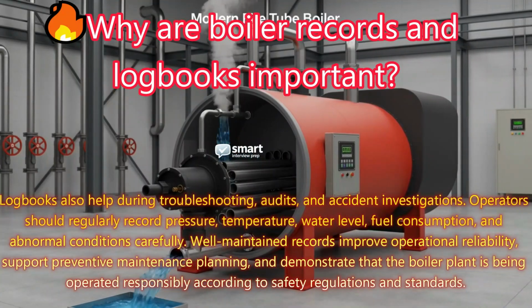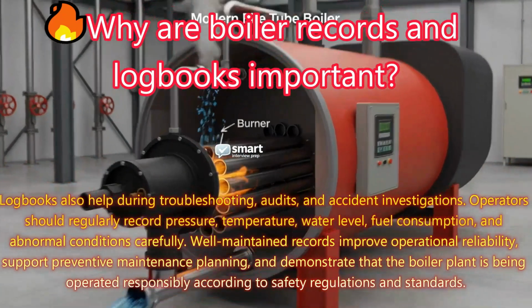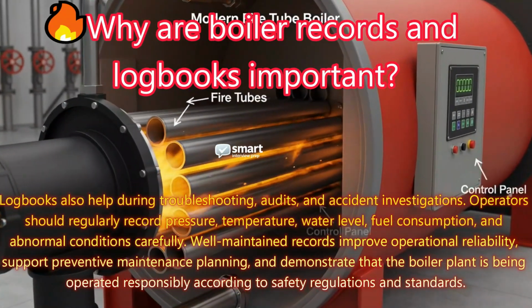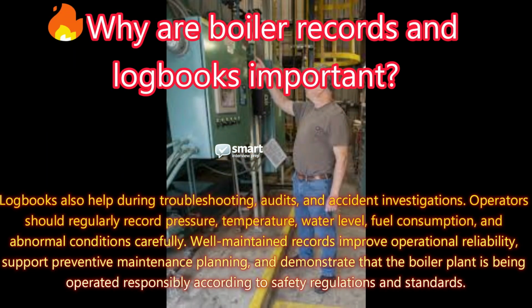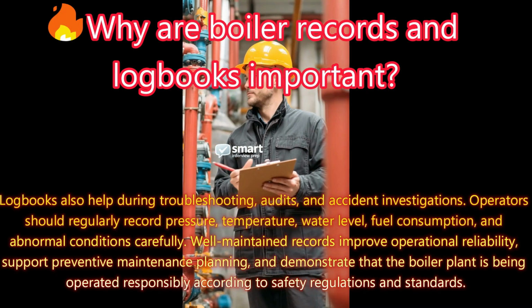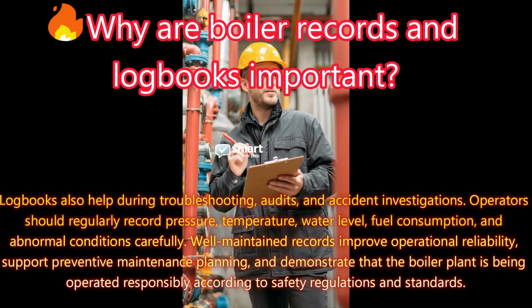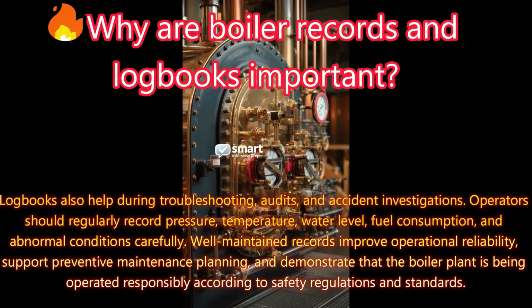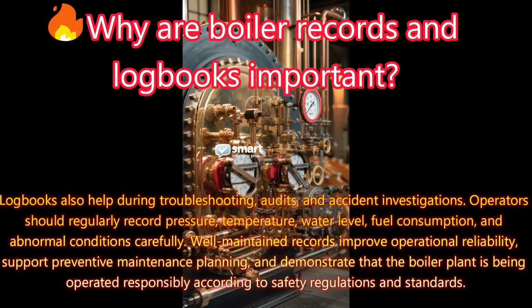Operators should regularly record pressure, temperature, water level, fuel consumption, and abnormal conditions carefully. Well-maintained records improve operational reliability, support preventive maintenance planning, and demonstrate that the boiler plant is being operated responsibly according to safety regulations and standards.